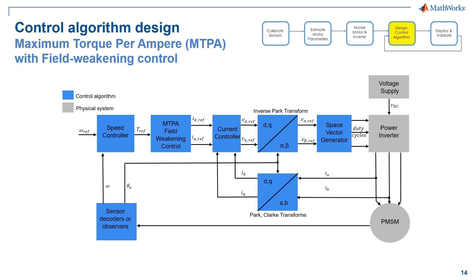Instead of showing you a basic implementation of field orientation control, I would like to show you how we design maximum torque per ampere — MTPA — with field weakening control. The output of the speed controller and the input of the current controller are embedded with MTPA and field weakening. The current references for Q and D-axis are calculated based on MTPA and field weakening algorithms to achieve maximum torque and minimum losses.